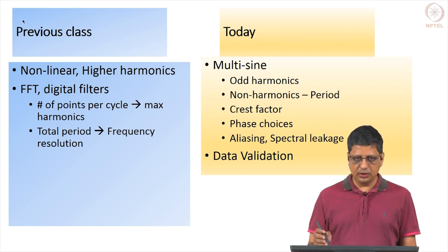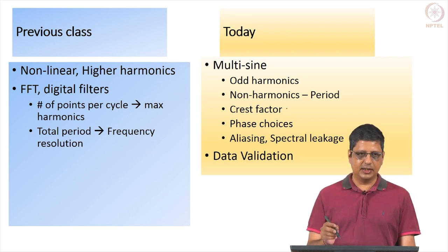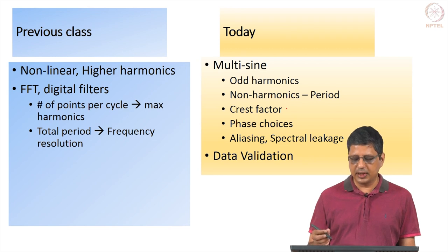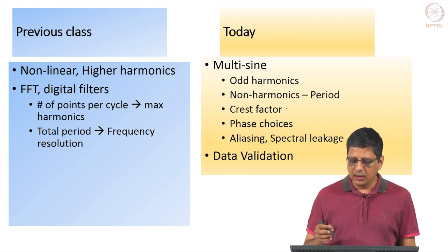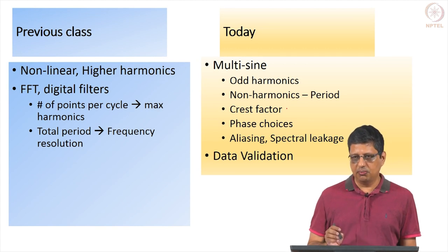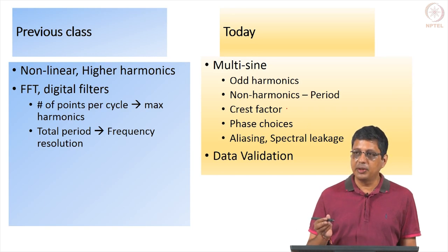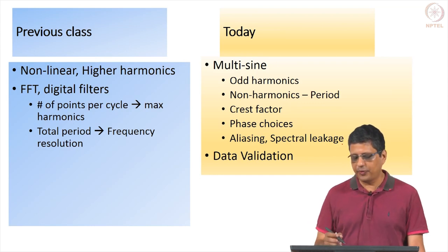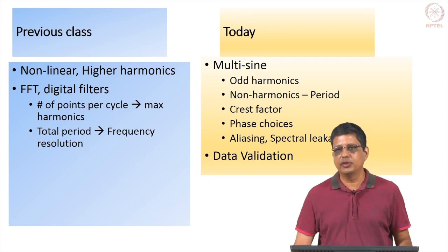Non-harmonics are also used — meaning they are not integer multiples of the base frequency. Crest factor is a parameter that one should know. It decides whether nonlinear effects may show up in the result or not. When you use non-harmonics, there is a problem in measuring and extracting the impedance correctly at those frequencies. If we have time, we will also start with data validation.